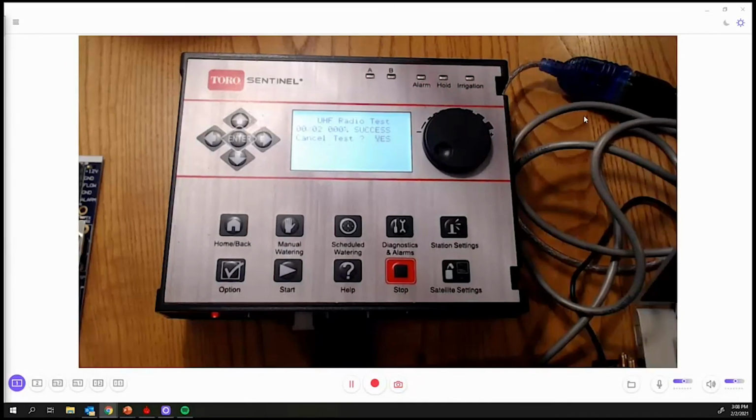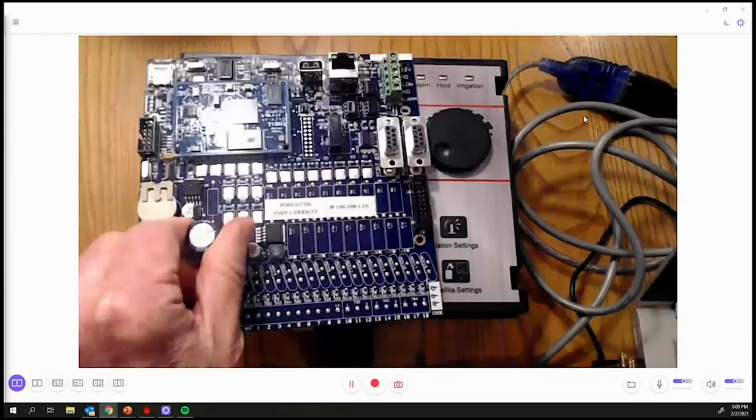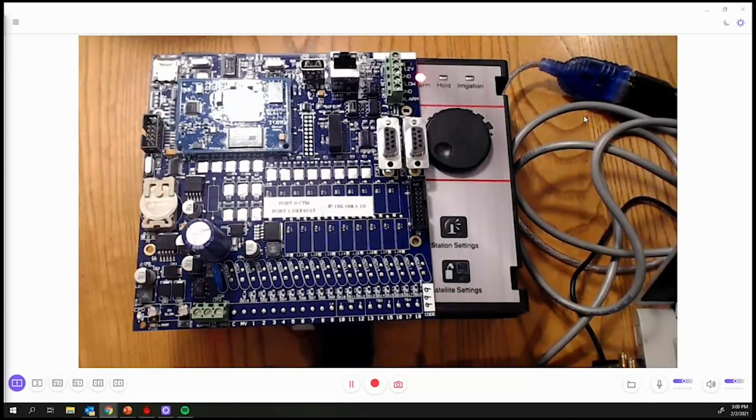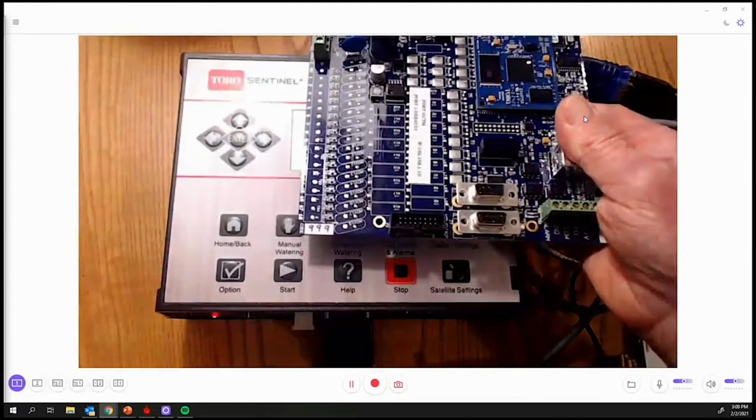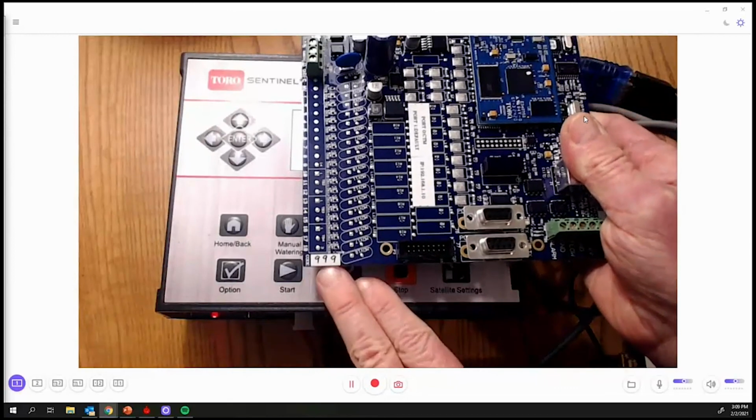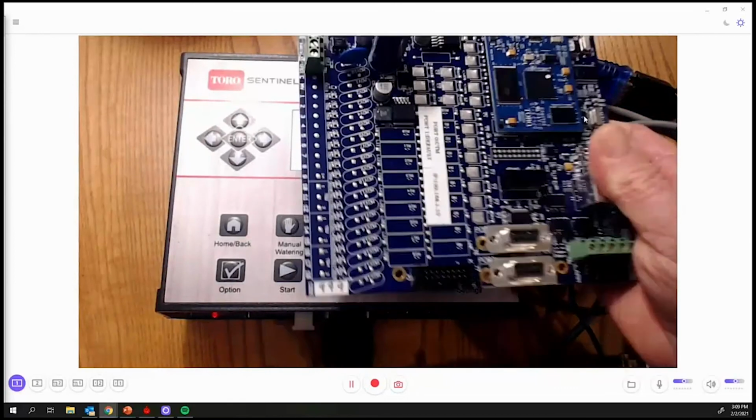So I stopped the communication after 2. But it would essentially transmit out of the radio on this controller to another controller that's locally installed, or it could be a CTM you have up on top of a building. Doesn't matter. Now, I should tell you that the CTM has a unit code just like a controller. You notice right there in that corner, it says 999. That's the default unit code it comes with.